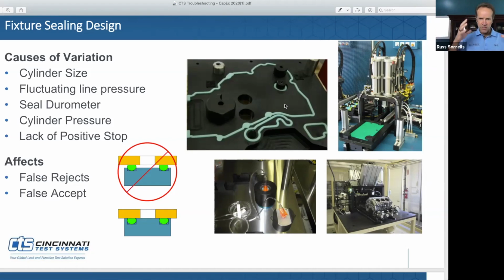Yeah, so I always try to get customers to wrap their mind around the fact that we are measuring pressure change, pressure change, pressure change, and anything that affects the pressure inside the part, whether it be heat, fluctuation of air pressure in the facility, or barometric pressure changes. I mean, we've seen it all, right? Right. Well, another way to visualize this is as a volume. If you have 1 millimeter of movement across that 20 square inches of surface, that equates to a volumetric change, and that's measured, like you said, with a pressure change correlated to a volumetric flow rate. And the sensitivity of the instrumentation is just tremendous. It picks it up because that's what we want it to do. We need it to in order to differentiate between these very small leak rates.